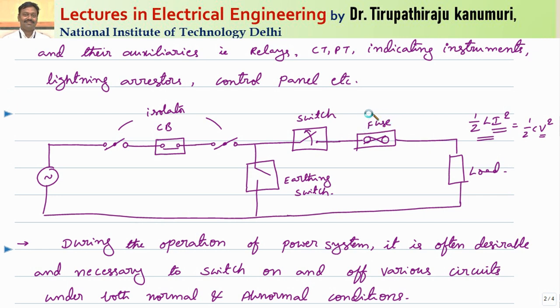What happens when you go for high voltage and high current applications? The thickness or size of the fuse element depends on the current carrying capacity, so as the current increases, the size and cost of the fuse element automatically increase. As the voltage is increased, in order to provide proper insulation between the contacts when the fuse element is blown, air has a dielectric strength of only 30 kV per centimeter. So as the voltage increases, the gap between the contacts increases, and automatically the size and cost of your fuse and switch increase. That is why this switch and fuse arrangement is used only for low voltage, low current rating equipment, and where continuity of supply is not a major concern.